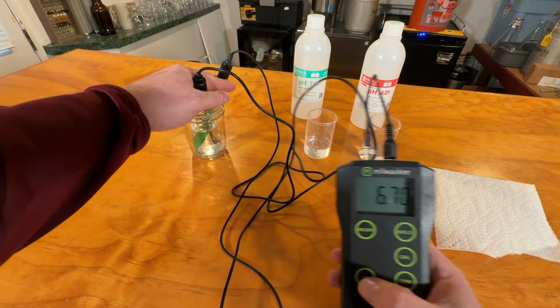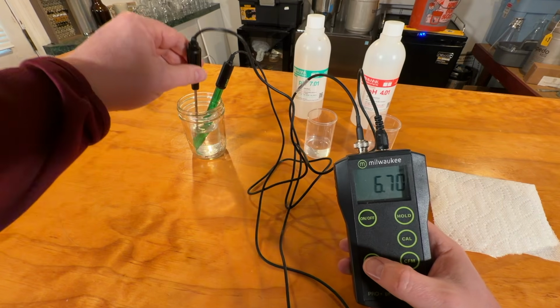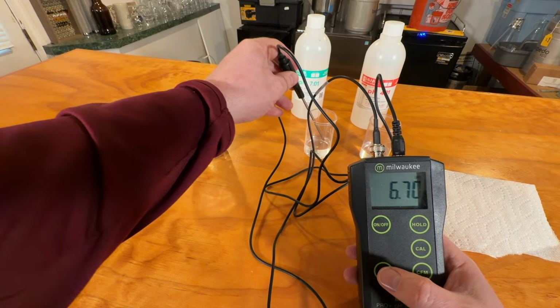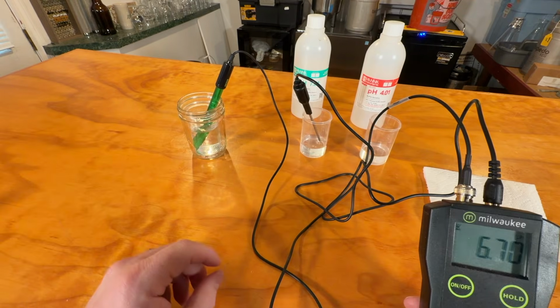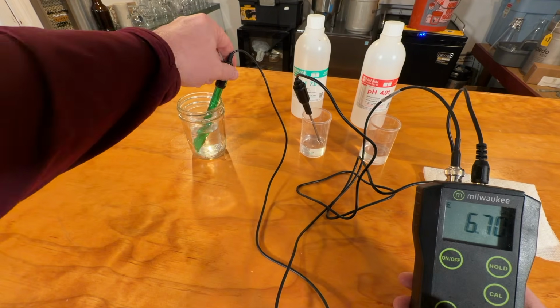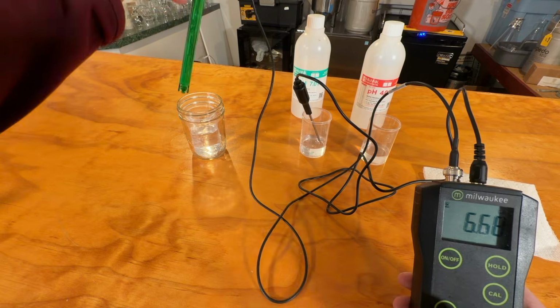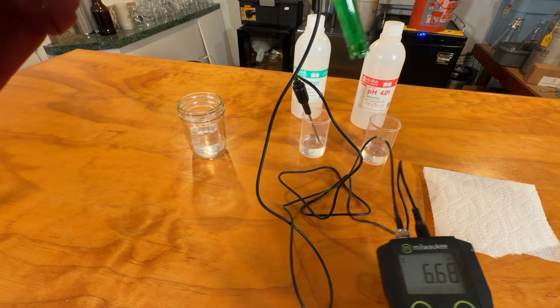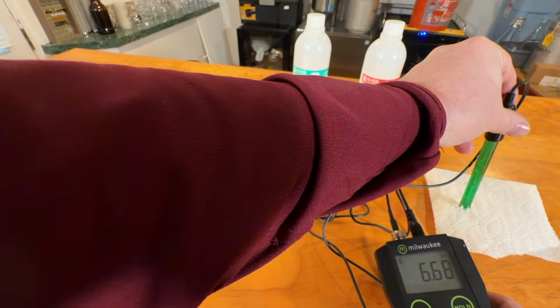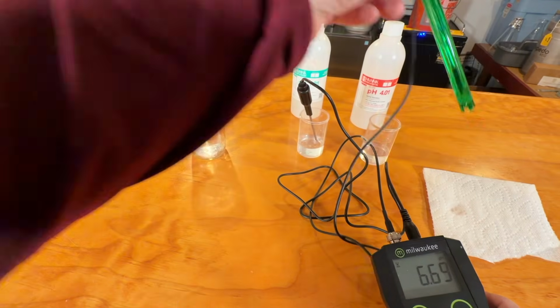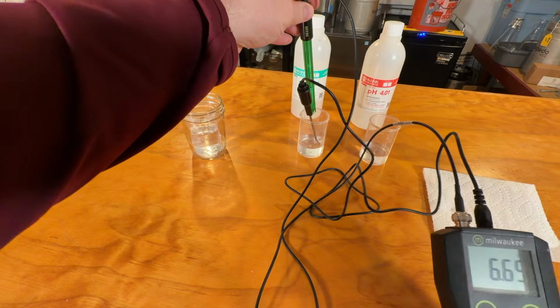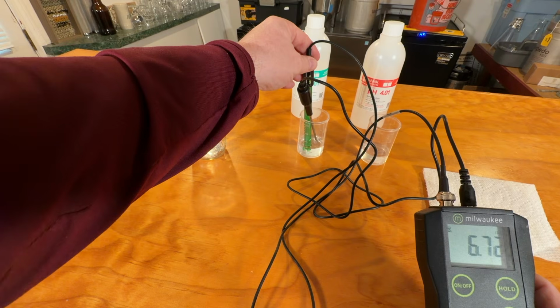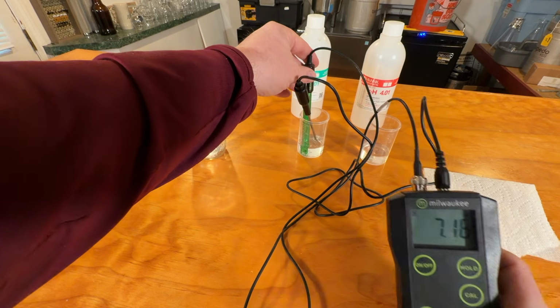So to take our first measurement, to get ready to do calibration, I'm going to take this out and put it into the pH 7 solution. I'm going to try to do this without knocking it over so you can see it. Then I'm going to take this, and I'm holding the pH meter at the same time, and dab it off on the paper towel just to get some of the excess water off so I don't upset my pH solution too much, which shouldn't happen.